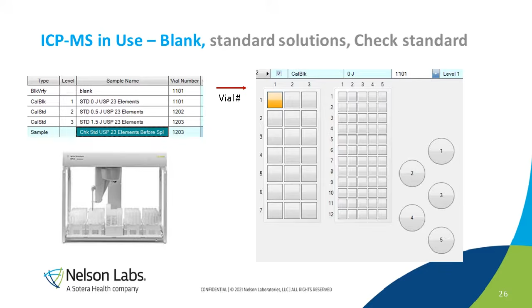So I just show the actual tuning record in that regard, and based on this, all passed. So I should say, all compounds. But actually, where did it come from? We get this tuning report when we do the tuning work. From here, we can check these numbers, and now, since all this verification and tuning passed the requirement, now we can use it. So now I'm showing this actually in use, and obviously the sequence starts with a blank injection, and then standard calibration, and then check standard verification. Then once all this is properly acquired, we can move on to sample injection.